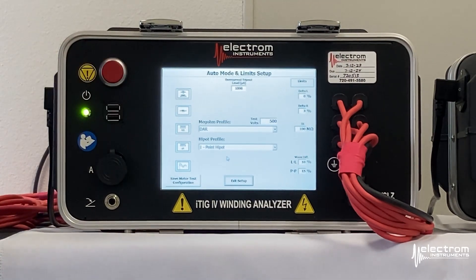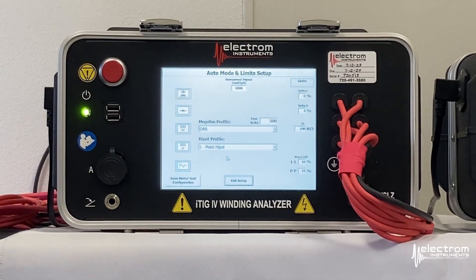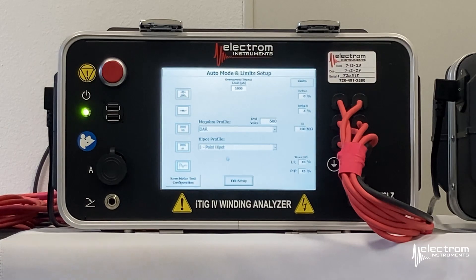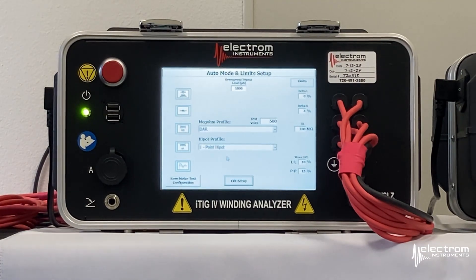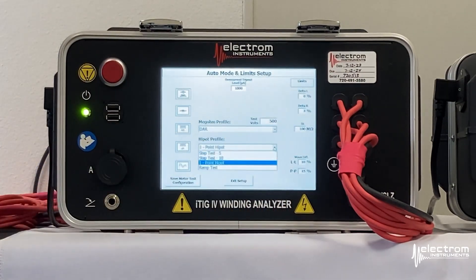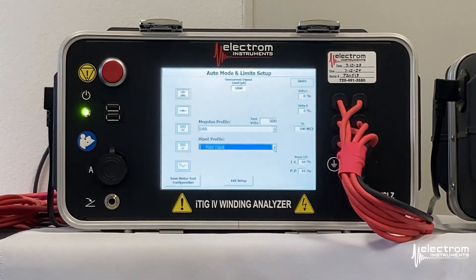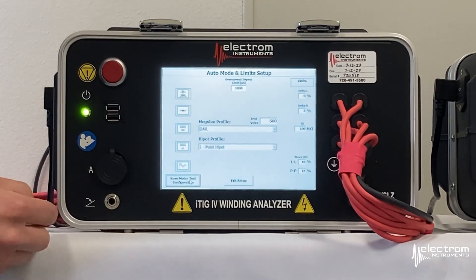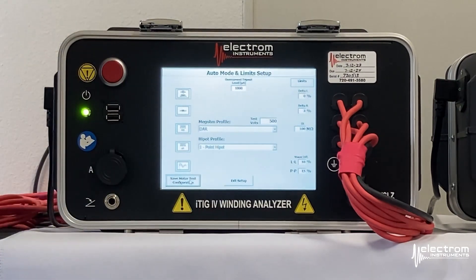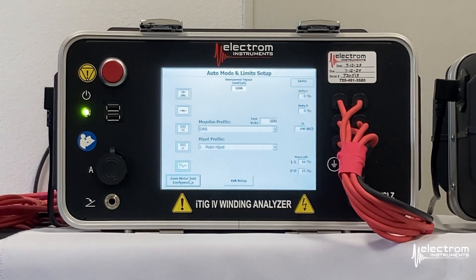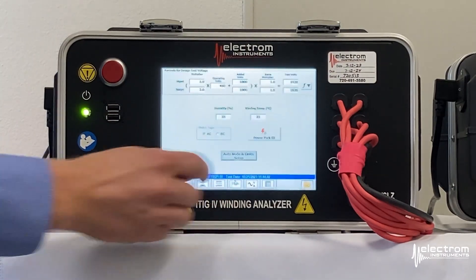We will run a one-minute dielectric absorption ratio test for the megaohm or insulation resistance test. You could select a PI, for example, if you're testing a larger motor, and we will do a one-point hypot — also a one-minute test. You can use the drop-down menu to select different test profiles including a five-point, ten-point step test, or a ramp test. This is the same motor test configuration, meaning it's predefined for the serial number next time you test it — no setup required. Exit setup.